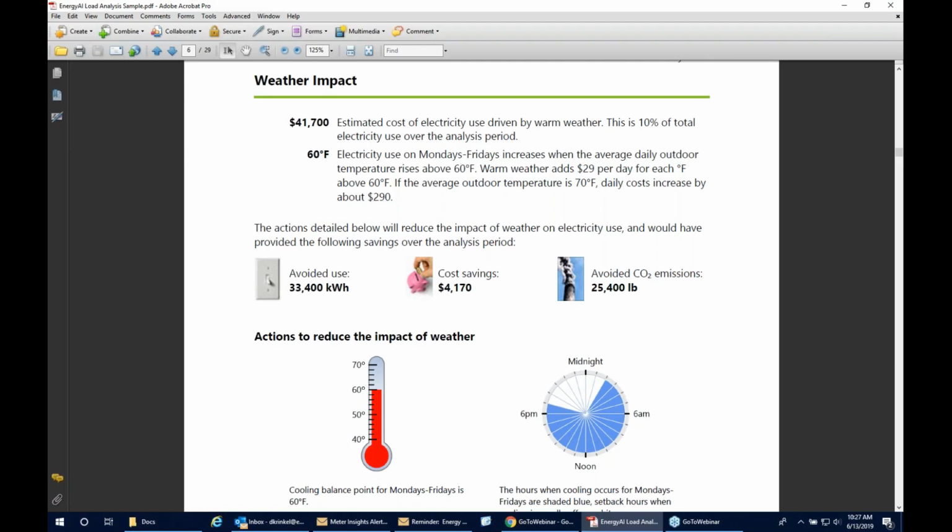We have a few different tweaks to it in that we do the weather correlation by day of week type. And what we mean by that in this example is we would do separate correlations for weekdays versus weekends. So the church example I gave a few minutes ago, where they have high use on Sundays, lower use on other days of the week.